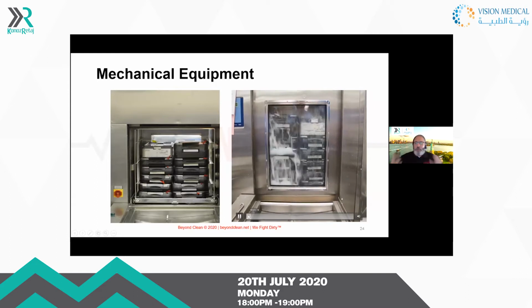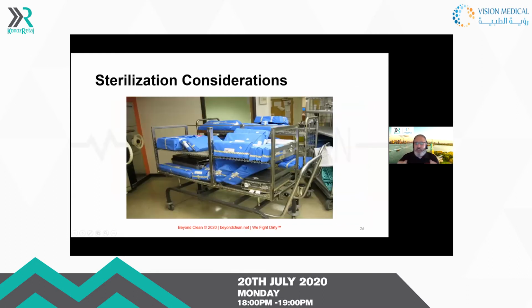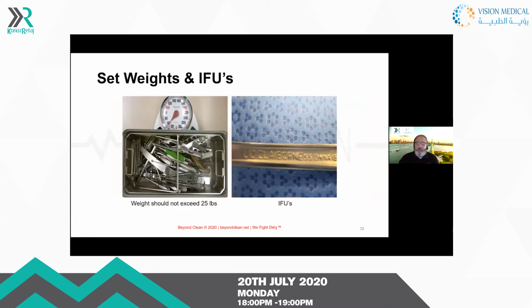So also we know that an instrument set should never exceed 25 pounds. And if they do, they can impact the sterilization efficacy. And as you see again on the left, we have an instrument tray that is almost 40 pounds here in the US, which is not good. And then I always kind of laugh with my customers and say, Liz Claiborne on the right, I'm positive she does not have an IFU, so we should not be placing instruments in a set that do not have IFUs.